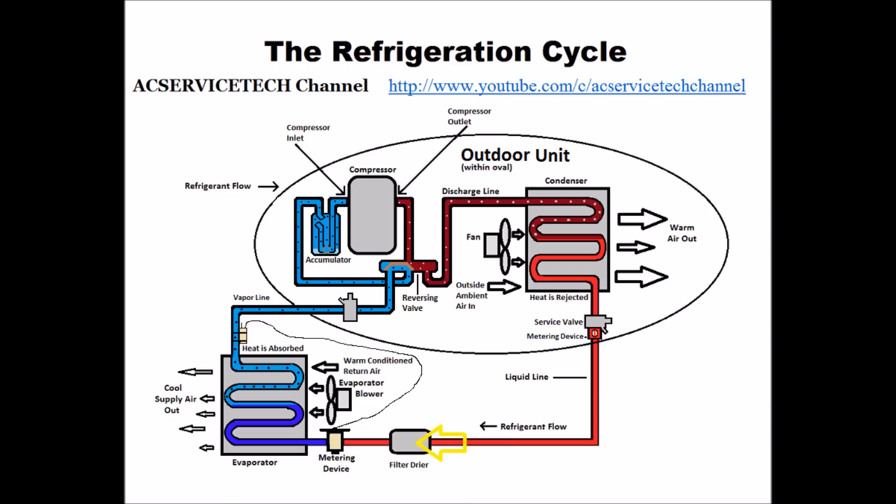It then goes through the filter dryer where it collects any contaminants and water vapor. The filter dryer's job is mainly to hold water vapor and it has a fixed capacity — you don't want water mixing with the refrigerant because it can turn into alcohol and acids. It continues as high pressure, high temperature liquid refrigerant and hits the metering device, which in this case is a thermostatic expansion valve. The TXV's job is to maintain a certain amount of superheat across the evaporator coil. There's a pressure drop there — it turns the high pressure, high temperature liquid refrigerant into 80% liquid, 20% flash gas by reducing the pressure.